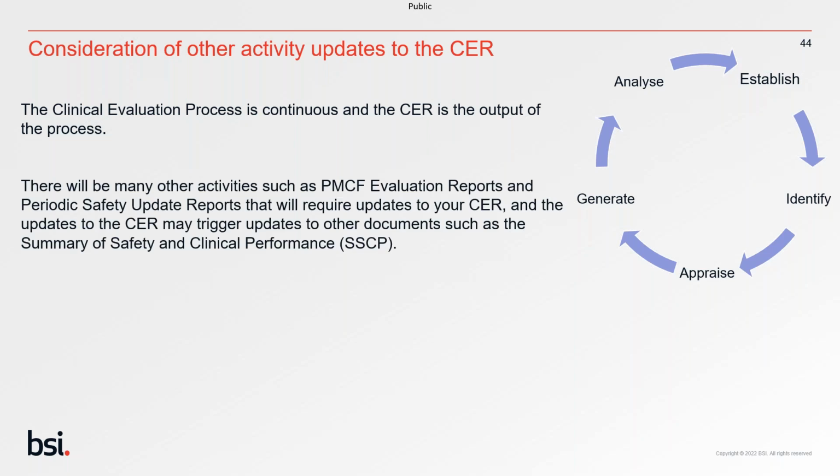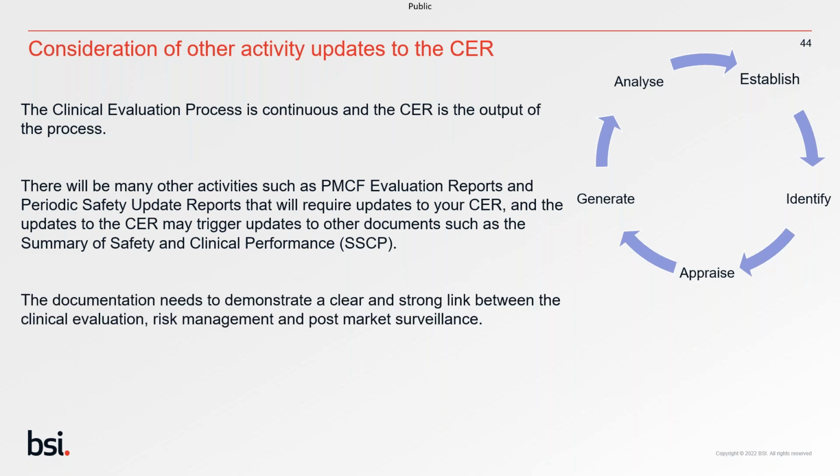And there will be many activities that feed into your clinical evaluation process, such as your post-market clinical follow-up, and what feeds out of that is also the evaluation reports. And sometimes there can be requirements to other documentation. So it's really important to think about the bigger picture. Even though we have our QMS procedures, it's very clear in your documentation that we need to see that strong link between the clinical evaluation, risk management, and post-market surveillance.